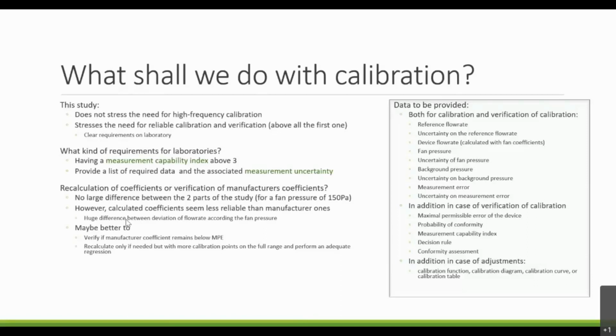And the last question is, what should be done during the calibration? Shall we recalculate the coefficients, like it is done in the UK, or only verify manufacturer coefficients, and if they are still good, keep them, like it is done in France? We have found out that there is no large difference between the two parts of the study for a fan pressure of 150 pascal. However, at the beginning, we have shown that calculated coefficients seem less reliable than manufacturer ones, because when we change this pressure to 150 pascal, the results also change a lot.